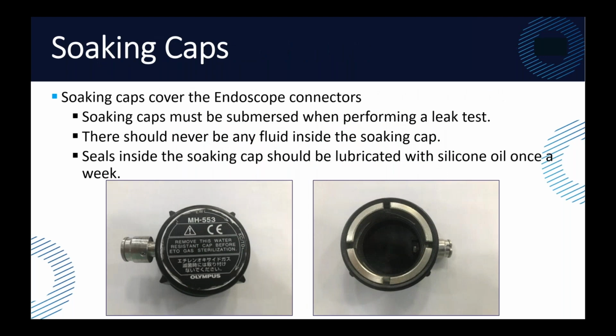Again, something else that is very specific to endoscopes are soaking caps. So when they're putting the endoscope in to be processed and cleaned, there are certain areas that need to be capped off and sealed with the soaking caps. If not, they're going to destroy the endoscope by putting it in there. But a couple things that need to be checked: there are seals on these soaking caps, and they need to be checked to make sure that they don't have any holes or tears in them. And they actually should be lubricated with silicone oil. Our endoscopy repair lab says once a week. I doubt that happens pretty much anywhere, just knowing the nature of people. I know I have a pool, and I'm supposed to grease those O-rings like every year, and I don't know that I do that either. But while it's soaking, that's also when they would do an electrical safety test on it as well. If those caps aren't tight, then water's going to get in there. They're also, generally speaking, going to fail safety testing.